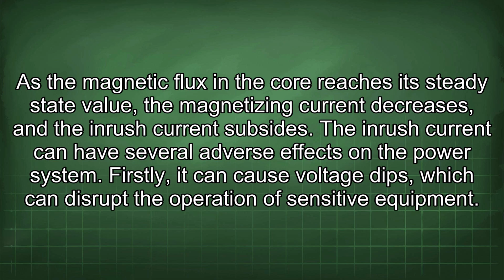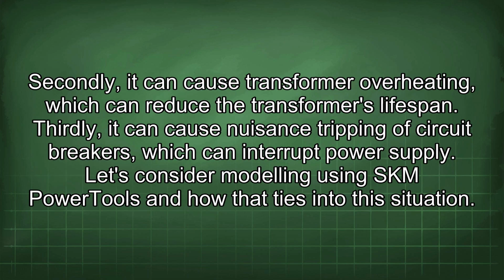The inrush current can have several adverse effects on the power system. Firstly, it can cause voltage dips, which can disrupt the operation of sensitive equipment. Secondly, it can cause transformer overheating, which can reduce the transformer's lifespan. Thirdly, it can cause nuisance tripping of circuit breakers, which can interrupt power supply.